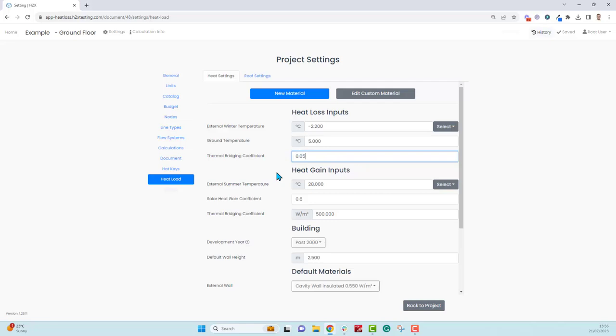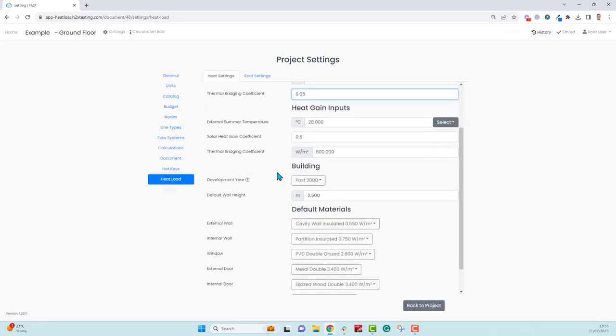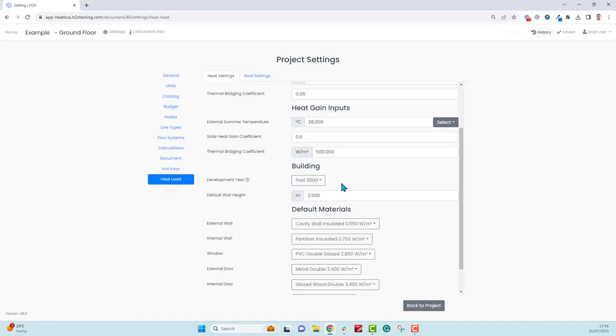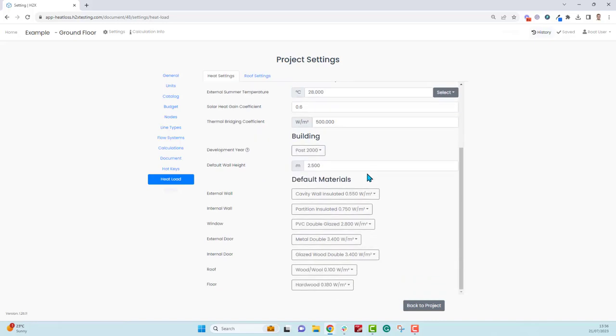Set to five percent here but feel free to change it. Ignore the heat gain inputs because that is for heat load calculations which we're not covering in this video. For the building you can choose what year it was built and this will inform the number of air changes per hour. The more modern the building, the less air changes and less heat loss. You can set the default wall height, then we have a list of materials for each component that you can draw with.